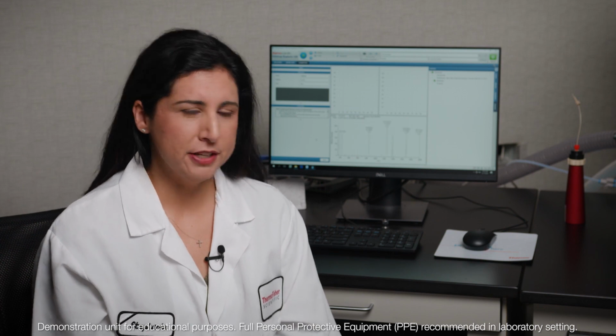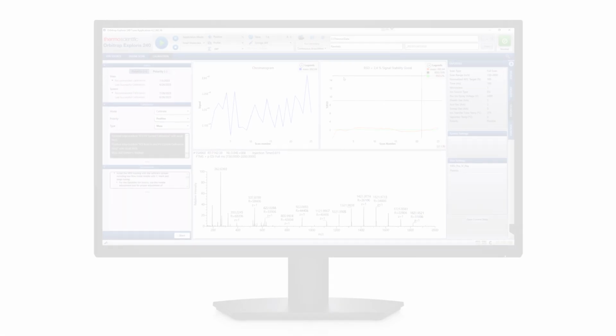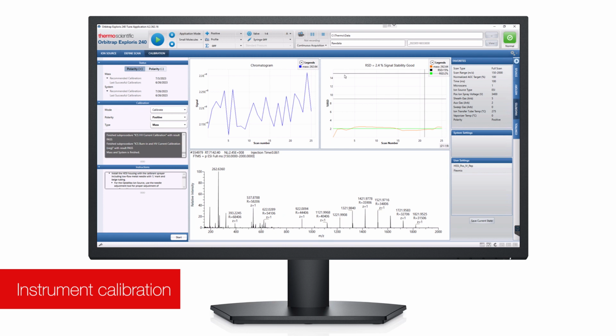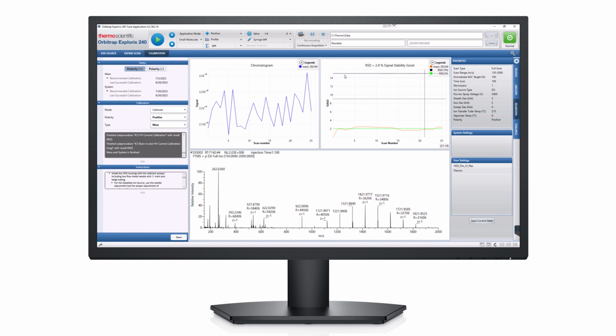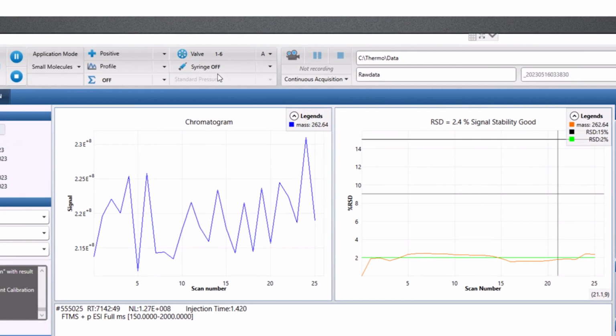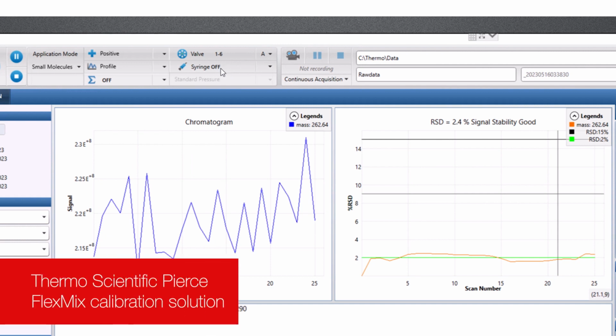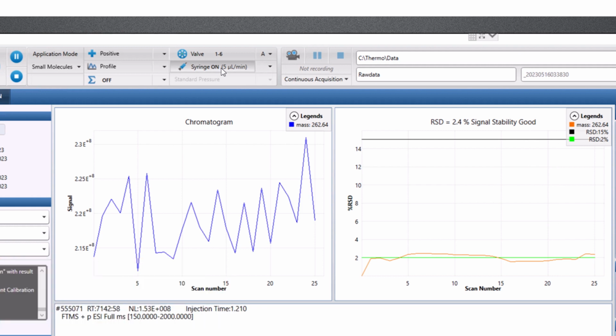Now I'm sitting here in front of the instrument control computer, and I'm going to go ahead and show you mass calibration. And this is something that was made much more simple on this generation of instruments. So let's go ahead and take a look. So here we're going to go ahead and calibrate our instrument, and we're going to do a simple positive mass calibration. The first step would be to connect a syringe with our calibrant flex mix solution. We can go ahead and turn the syringe on.